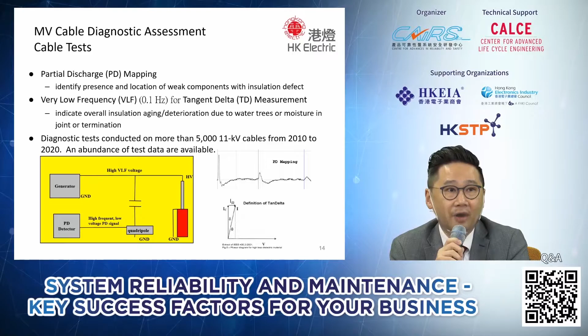In the past, we have conducted a lot of tests and collected a lot of test data, mainly in two areas: partial discharge mapping and very low frequency tangent delta measurements. These two tests have their unique functions, and they cannot replace each other. Partial discharge can locate the weak components in the cables or in any apparatus. Very low frequency cannot exactly pinpoint the fault location, but it can indicate the overall performance of the cables. With these two tests joined together, they supplement each other and provide very useful information to us.